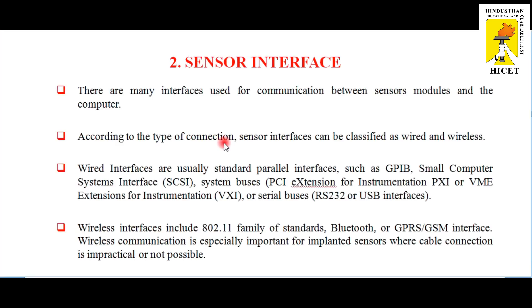The next important part of the virtual instrument is the sensor interface. There are many interfaces used for communication between the sensor module and the computer. According to the type of connection, sensor interfaces can be classified as wired and wireless. Wired interfaces are usually standard parallel interfaces such as GPIB, Small Computer System Interface (SCSI), system buses — for example, PCI Extension for Instrumentation (PXI) or VME Extension for Instrumentation (VXI) — or serial buses, for example RS-232 or USB interfaces.